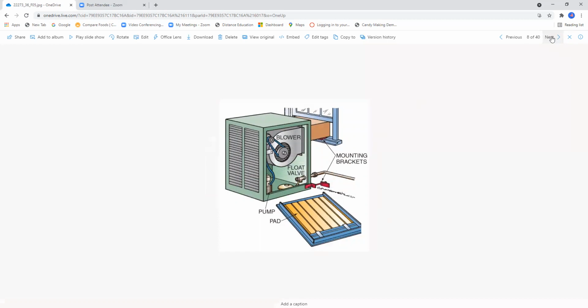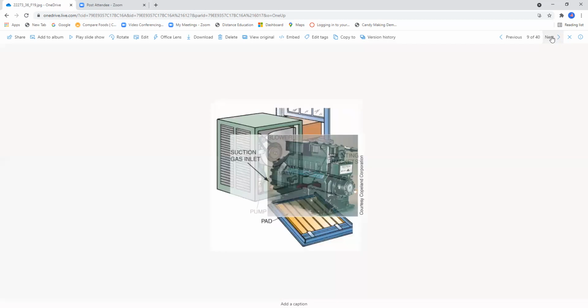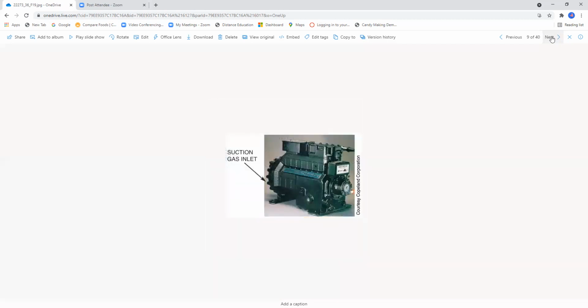Here we have a swamp cooler. This is a window mount we talked about in the previous presentation on the PowerPoint. Here I believe this is a Discus compressor from Copeland Corporation. Notice that the suction gas is going to be hooked up to this end bell right here, and then your discharge is going to be up here on the top of the valve plate. Over here we have what they call a Sentronic oil failure pressure switch. Down below here is the oil failure switch.